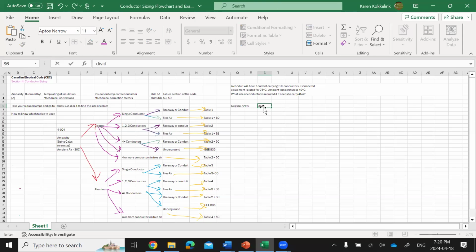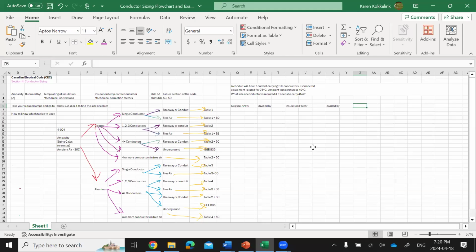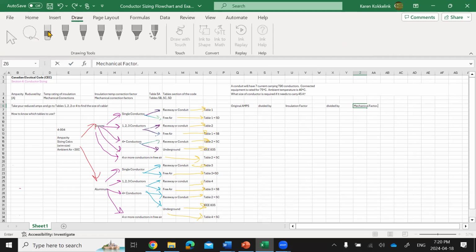So divided by the insulation factor, and also divided by the factor that I'm going to find in 5C, which is, what do I want to call that factor? Ampacity correction factor for number of conductors. I'm going to call it mechanical factor. And what this will all look like, if I draw it on here, I'd like to draw it as an equation. So I'd have my original amps.